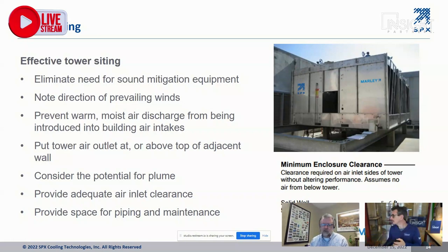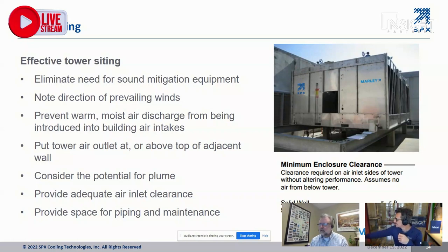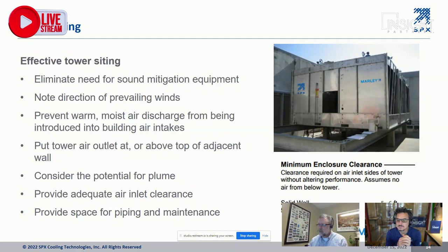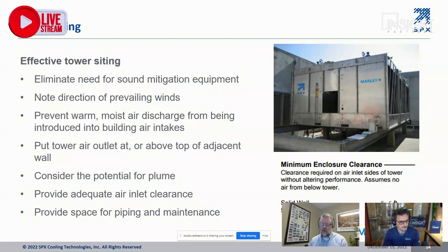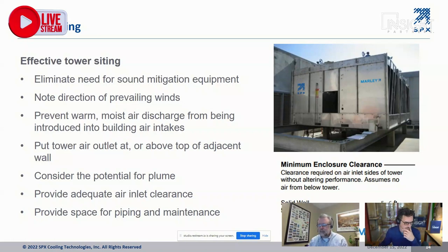You don't want to discharge cooling tower air back into your building — it's very humid and potentially could contain Legionella. Fan cylinder segments may need to be added to the top to ensure the discharge is at or above the enclosure wall. People often want to hide the cooling tower behind an enclosure wall, which is fine, but you need to ensure the wall is not so tall that the tower is in a deep well unable to get fresh air. Also ensure there's space for piping as well as maintenance, since some installations can be quite crowded.